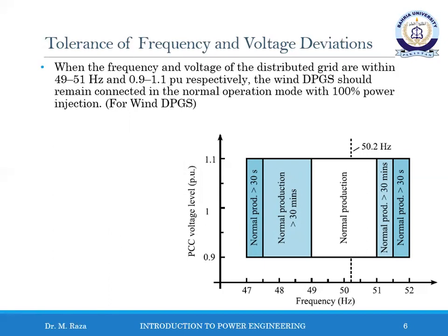When the grid frequency is in the range of 47.5 to 49 Hz or 51 to 51.5 Hz, then the generation system can remain connected to the network and produce normally for up to 30 minutes. Beyond this time, either production needs to be reduced or it must be disconnected completely. Similarly, when the grid frequency falls in the range of 47 to 47.5 Hz or 51.5 to 52 Hz, it can operate normally for up to 30 seconds but must be disconnected afterward. Once the grid frequency rises above 52 Hz or drops below 47 Hz, then the distribution generation system must be disconnected from the network immediately.